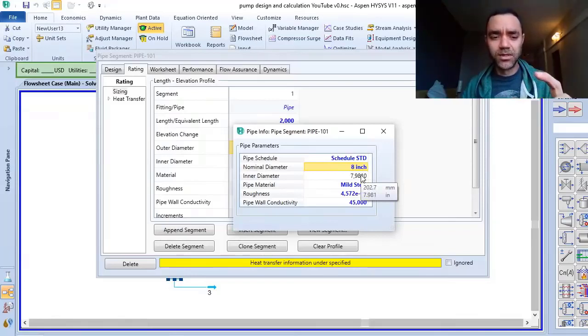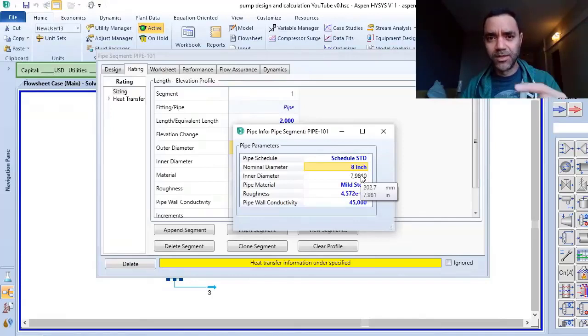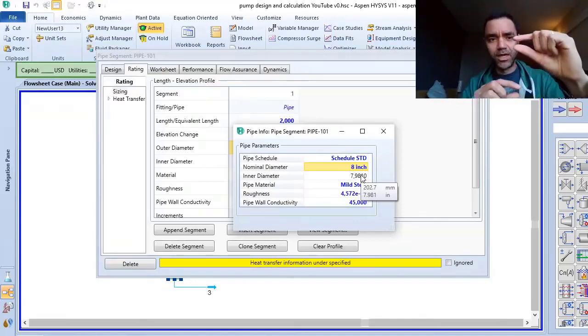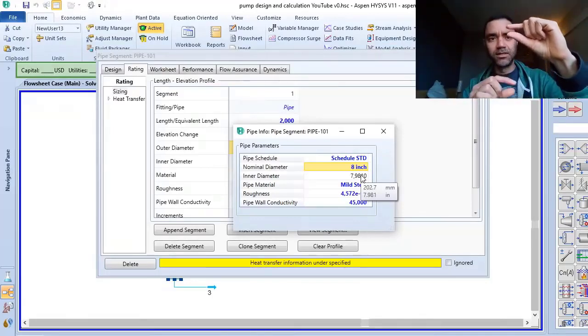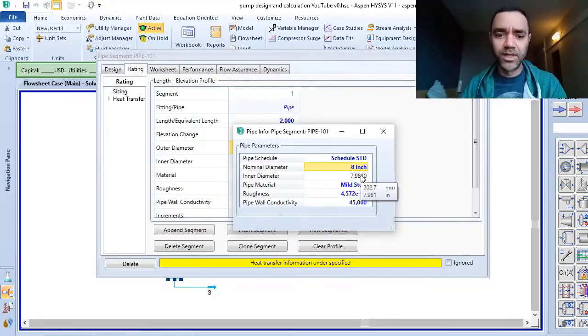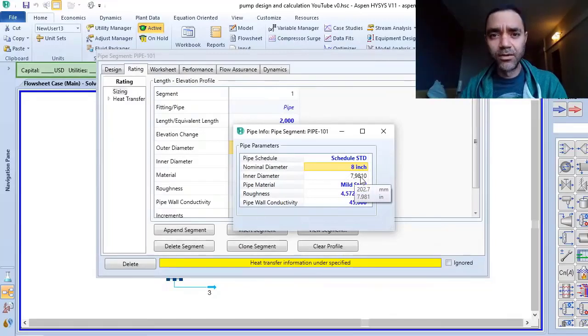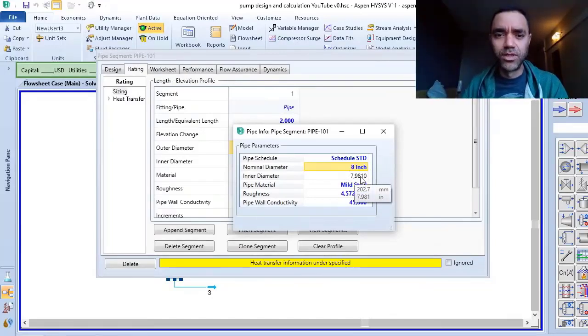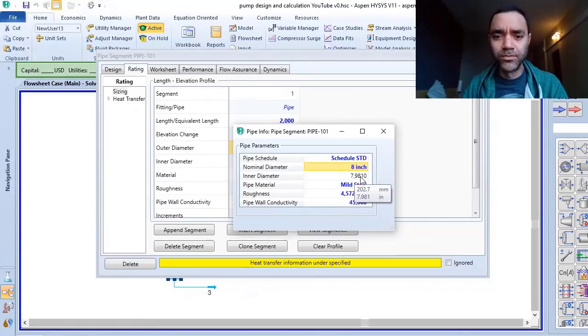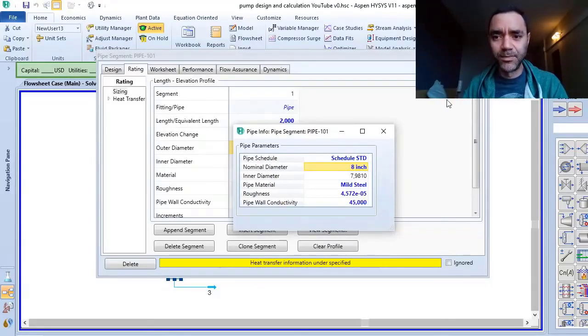So the outer diameter minus the thickness, two times the thickness because you have thickness on the top and on the bottom, you will have the inner diameter. And all the calculations related to the fluid flow is based on the inner diameter, not the outside diameter.